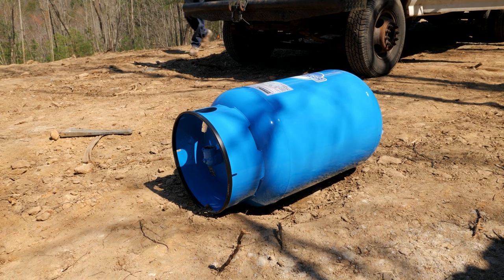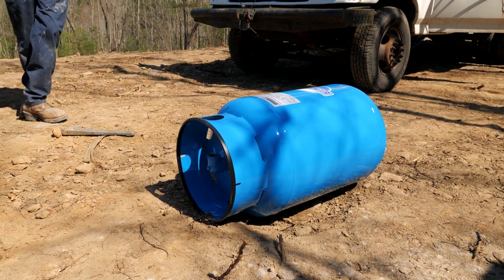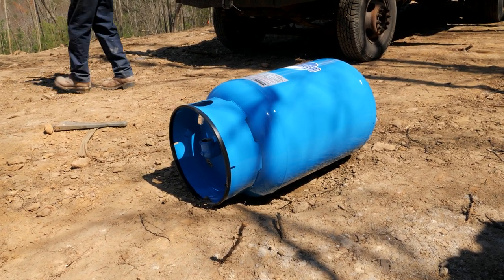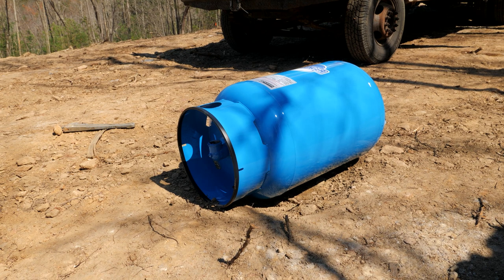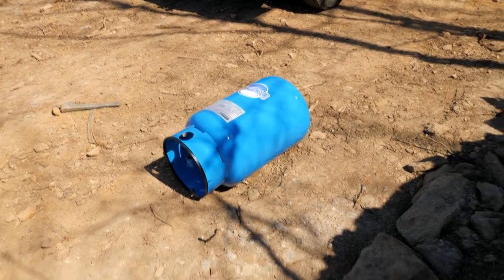I have literally taken Well-X-Trols out and put these in. Why? These Well-X-Trols they're making now, I don't use Well-X-Trols a lot, but the ones I have used and the ones I've had to replace have still been under warranty. Yep. They should not go bad in your warranty period.